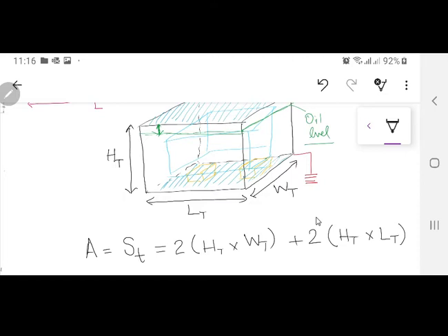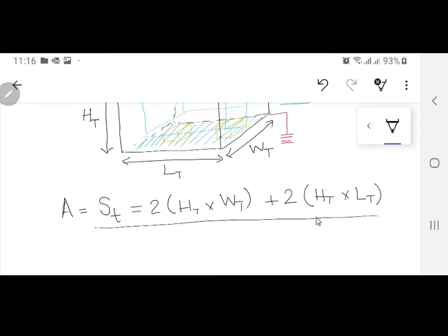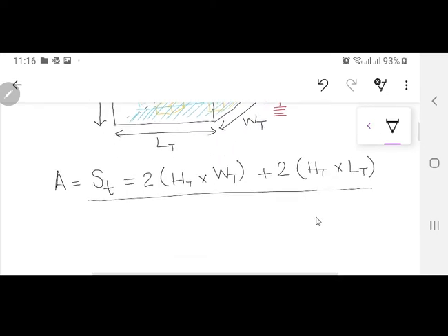This is not the actual surface area, but the effective surface area that is actually dissipating the heat. Now when you have found this ST total, you multiply ST by 12.5 watts per meter square per degree centigrade. What will this give you? This will tell you how many watts you are going to dissipate from the tank, per degree centigrade.